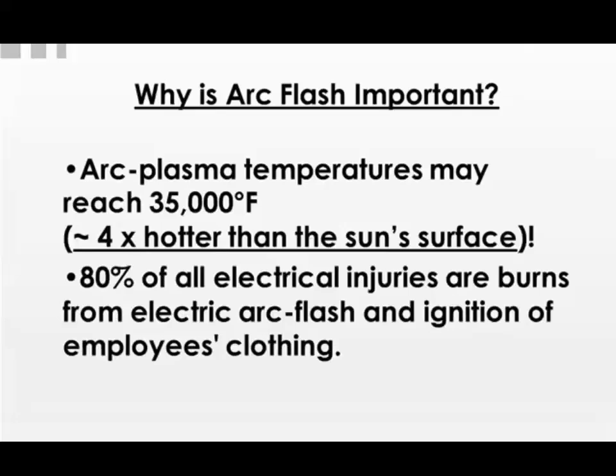And 80% of all electric injuries are burns from electric arc flash and ignition of employees' clothing. So you have the arc flash event, the explosion. We'll talk about some of the hazards associated with the arc flash. But again, very common, if somebody doesn't have the right arc flash personal protective equipment on, their clothing will catch on fire. If they have synthetic clothes underneath, even if it's an arc flash rated suit, any synthetic material can literally melt to the skin.